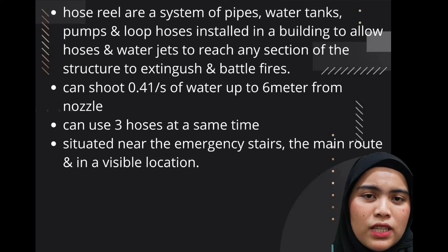Next, I will explain about fire equipment that must be in Hospital Taiping. Firstly is the hose reel. Hose reels are a system of pipes, water tank, pumps and looped hose installed in the building to allow hose and water jet to reach any section of the structure to extinguish and battle fire. In addition, the hose reel can shoot a water jet up to 6 meters from its nozzle, and may simultaneously use 3 hoses. This hose reel will also be situated near the emergency stair and the main route in a visible location. Next is the fire extinguisher in Hospital Taiping.